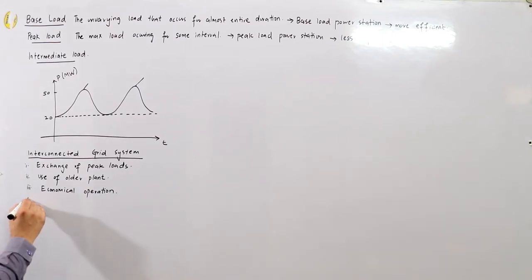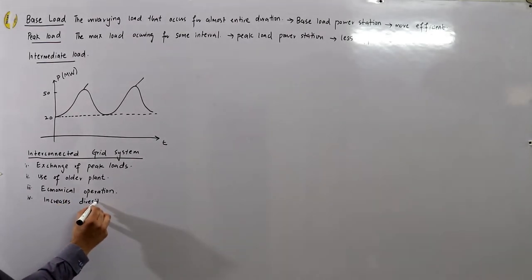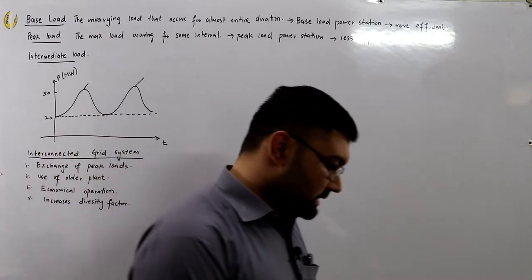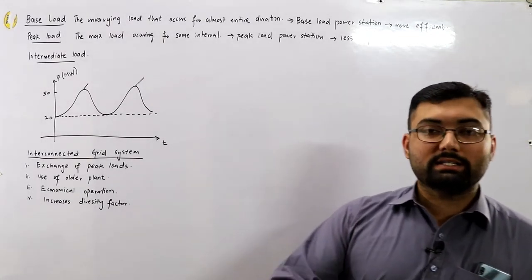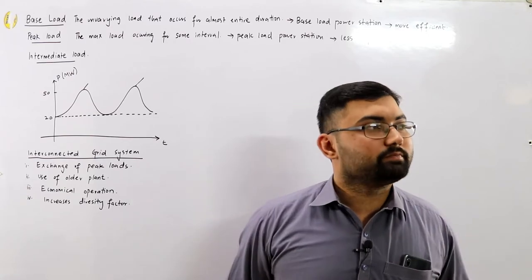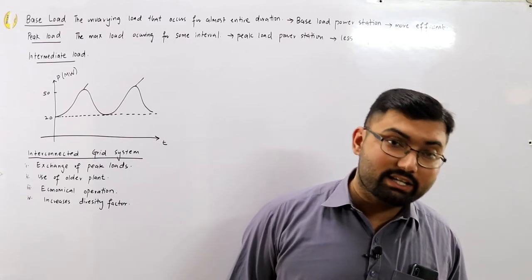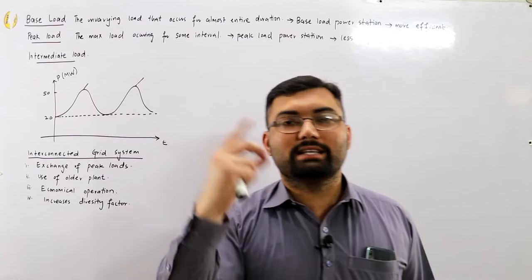The fourth benefit is that it increases the diversity factor. The maximum demand on the system is much reduced because the system now has a very large number of generating stations, so the summation of maximum demand across the entire system is comparatively much less than individual systems.